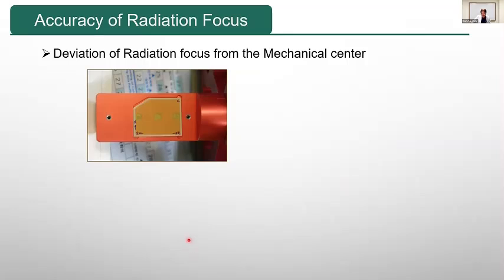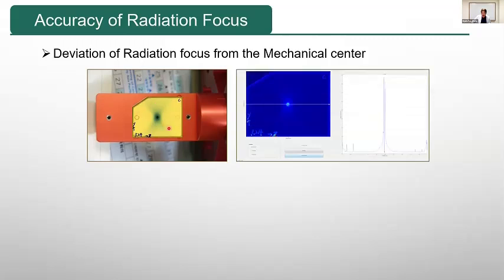Let's start with the accuracy of the radiation focus. It means that we check the conformity of the mechanical center and the radiological focus. The vendor provides a special tool like this. After we set a film here and push the button, there is a marker on the film, which means the mechanical center point of the machine. Then we irradiate the film with a 4 mm collimator. Then we have these images, and we analyze this film. There's a sharp valley here. This is the mechanical center, and the center of this peak is the radiological focus. So this mechanical center and this radiological focus must coincide.